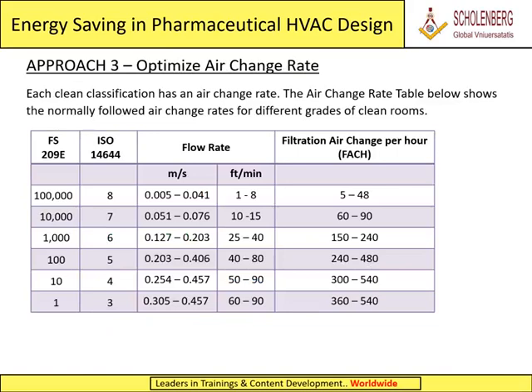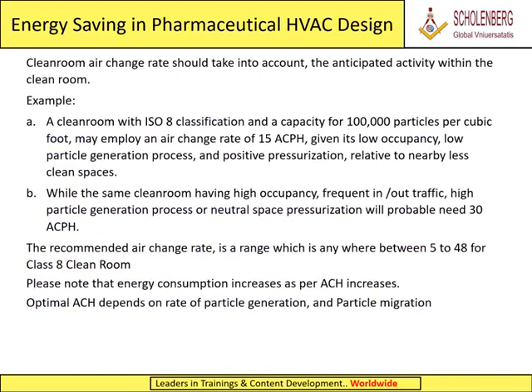Approach 3, optimize air change rate. Each clean classification has an air change rate. The air change rate table below shows the normally followed air change rates for different grades of clean rooms. Clean room air change rate should take into account the anticipated activity within the clean room. Example: a. A clean room with ISO 8 classification and a capacity for 100,000 particles per cubic foot may employ an air change rate of 15 ACPH, given its low occupancy, low particle generation process, and positive pressurization relative to nearby less clean spaces. b. While the same clean room having high occupancy, frequent in/out traffic, high particle generation process or neutral space pressurization will probably need 30 ACPH.